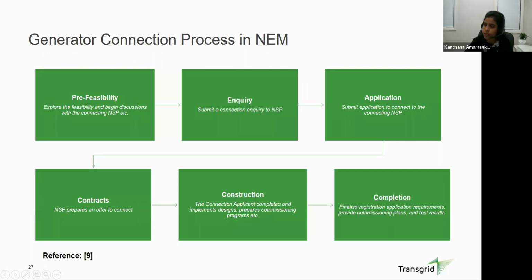What we would have in this connection inquiry response is usually a high-level connection arrangement, and it will also say whether there's sufficient capacity in the network for the connection. It will also have technical study requirements and technical performance requirements that the plant will have to meet. Those are the main items in the connection inquiry response. Apart from that, I mentioned the PIA, the preliminary impact assessment. It is also part of this connection inquiry stage. And one more thing we usually provide during connection inquiry is technical requirements, and sometimes things like harmonic emission limits and fault levels, basically the technical requirements that they have to comply with. So that's about the connection inquiry.